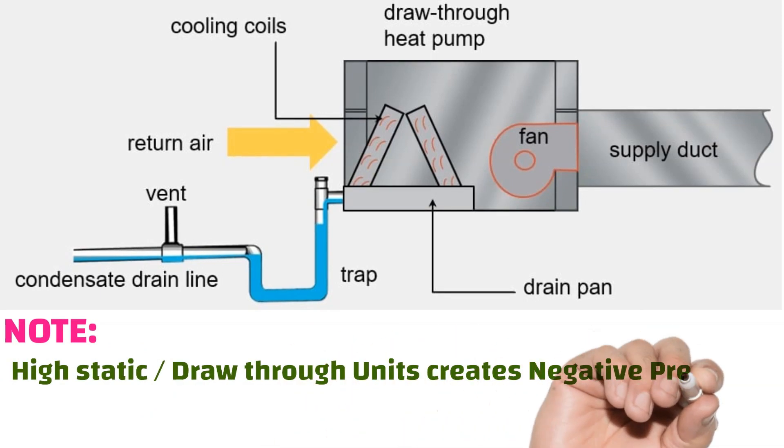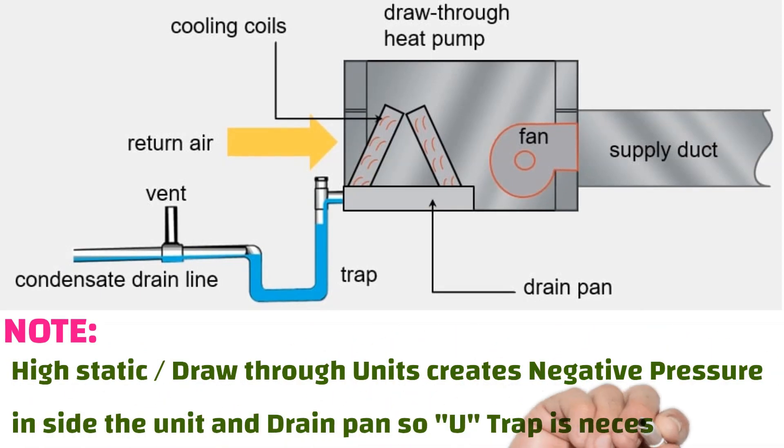High static and draw-through units create negative pressure inside the unit and drain pan. So a trap is necessary in the condensate drain pipe.